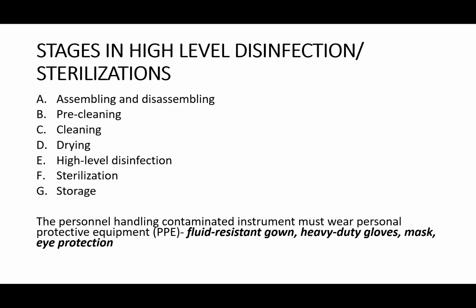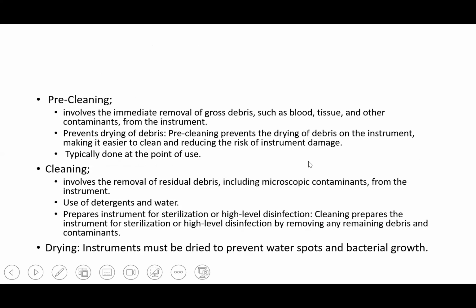So let us look at this individually. Now, for pre-cleaning, we mentioned that it involves the immediate removal of gross debris, such as blood, tissue, and other contaminants from the instrument to prevent drying of the debris. Pre-cleaning prevents the drying of debris on the instrument, making it easy to clean and reducing the risk of instrument damage. It's typically done at the point of use. Now, cleaning involves the removal of residual debris, including microscopic contaminants from the instrument. Of course, this uses detergents and water or other cleaning agents. It prepares the instrument for sterilization or high-level disinfection by removing any remaining debris or contaminants.